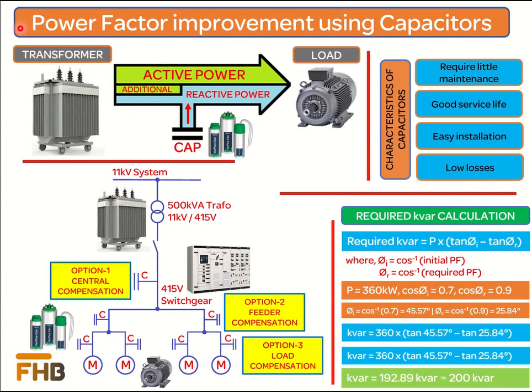The most commonly used method in industry for power factor correction is the installation of power factor correction capacitors. These capacitors supply positive reactive power to the system, partly or completely neutralizing the effect of negative reactive power demand of the load. With the supply of positive reactive power, the power factor improves and additional kVA capacity is freed in the installed equipment. Power factor correction capacitors require less maintenance, have a good service life of many years, are easy to install, and have low losses.